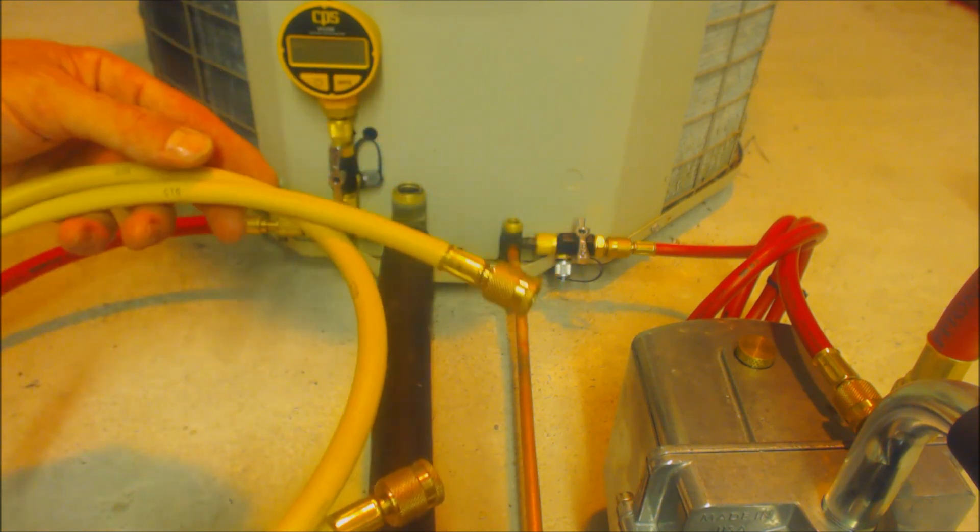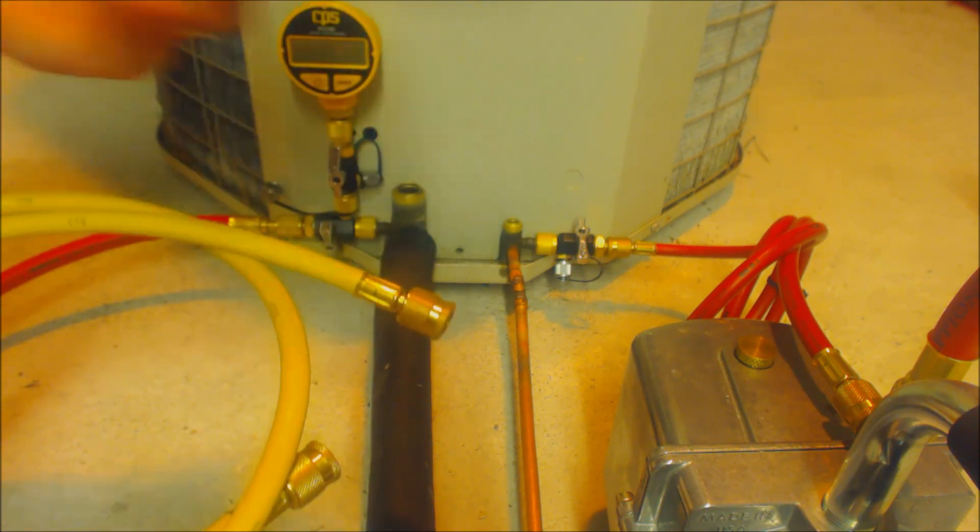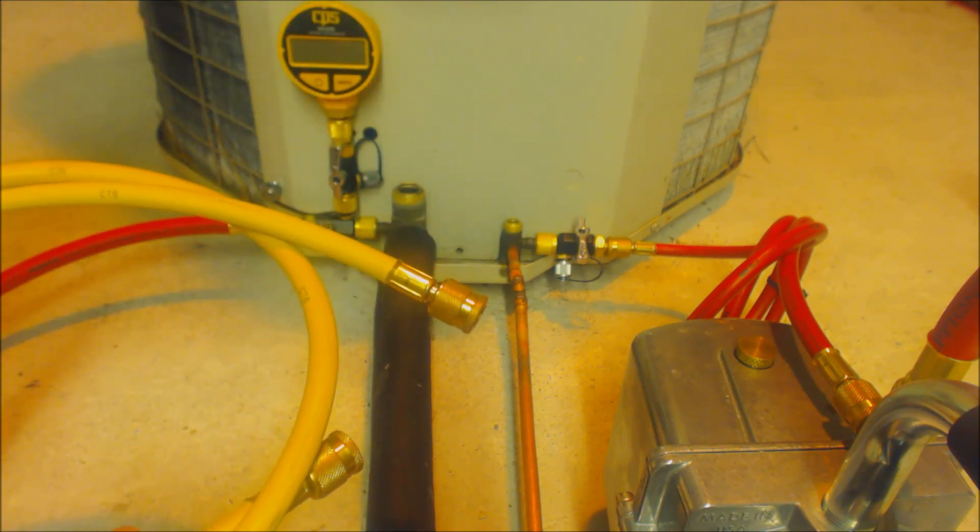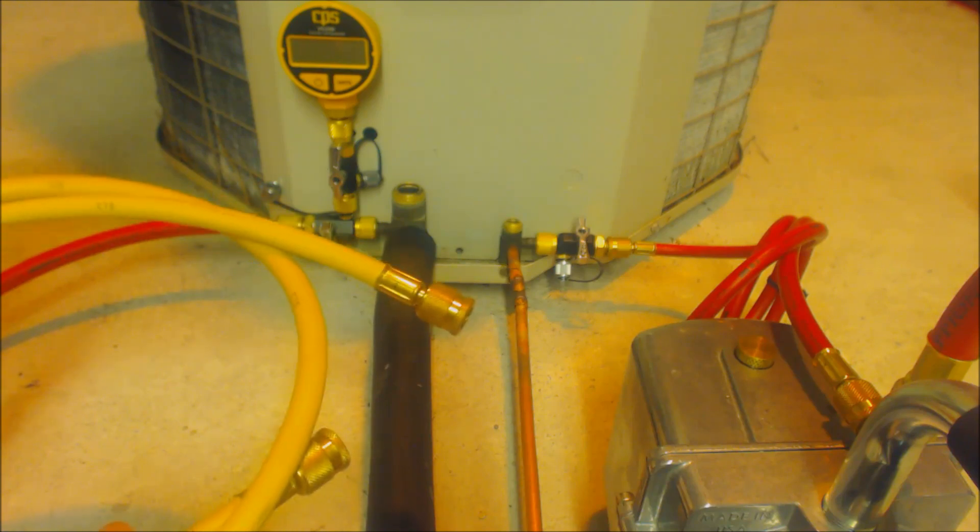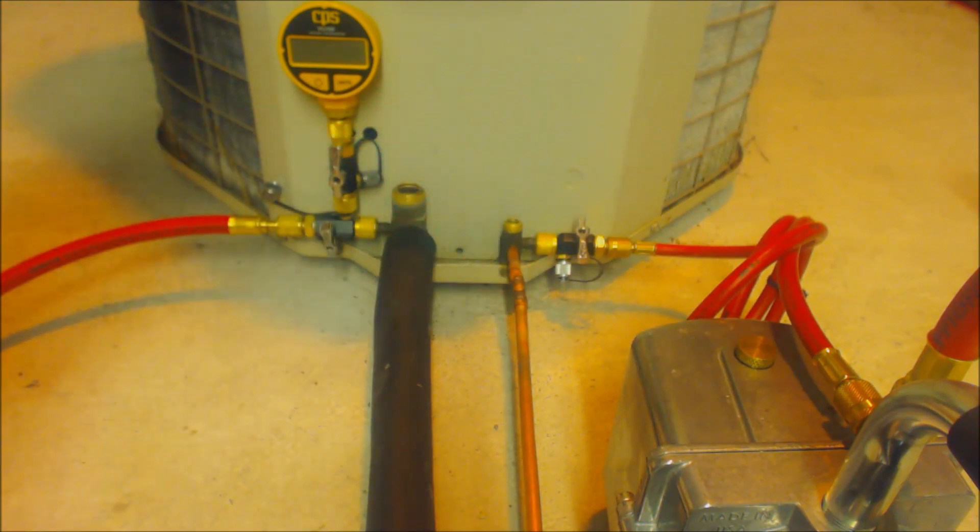So what I recommend is that you try not to go through the manifold set. You can, especially if it's a new set and it's nice and tight, but it's best to just attach it from the vacuum pump directly to the system in order to get a deep vacuum and to take some of the worries out of your head.